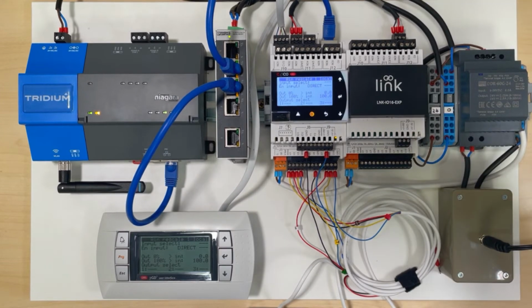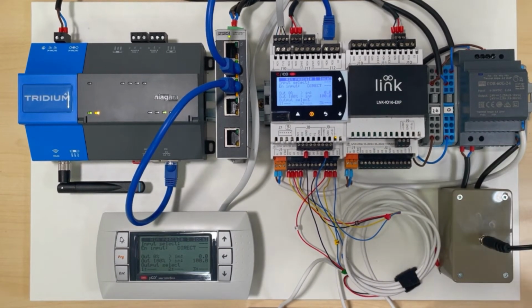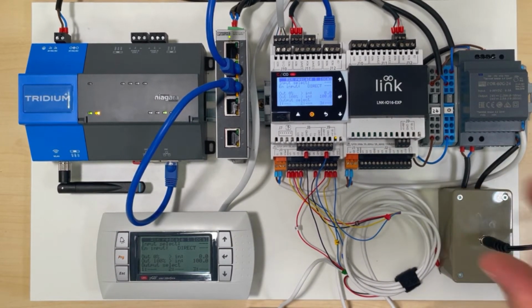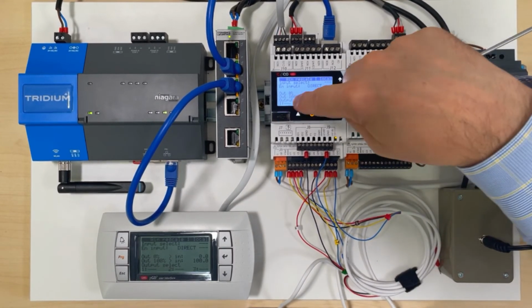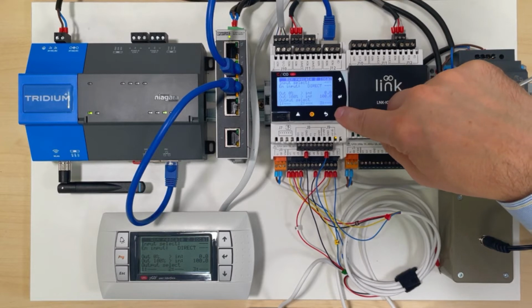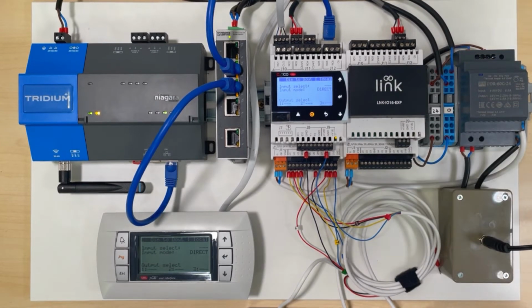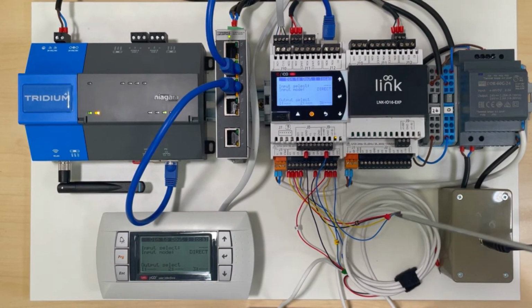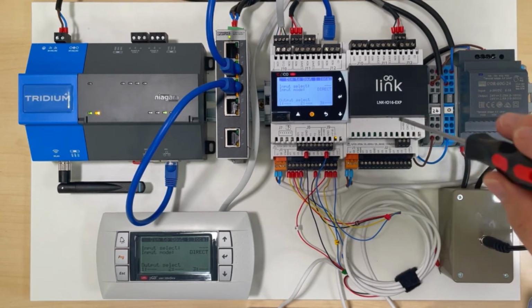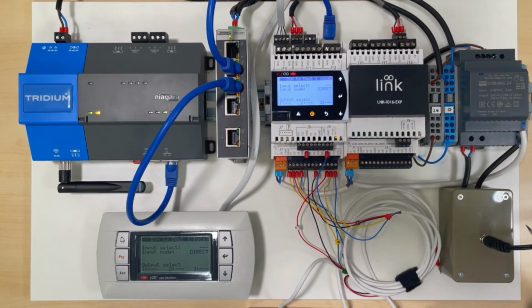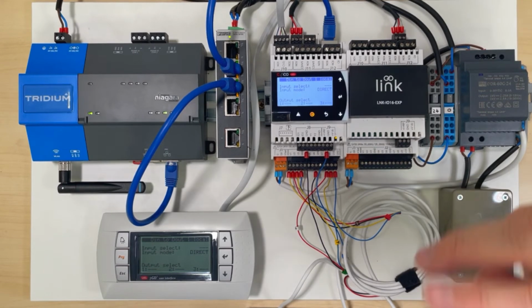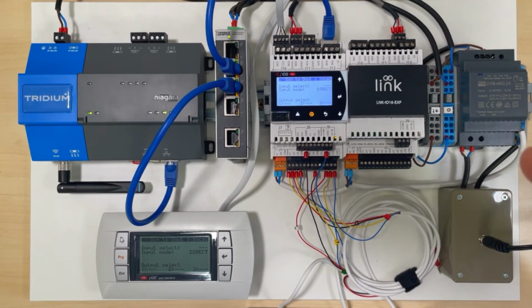You could do an analog input rescale, so what that will do is take a 0 to 10 volt and it will convert it to a 0 to 10 volt on 1 or up to 3 actually of the outputs that you can set down the bottom here. Okay, so there's 2 of those. There's a dig in to dig out, so that's just basically a digital input being mapped through to up to 3 digital outputs, and you can reverse it, so when the digital input is on, it can be direct and the digital outputs will be on, or it could be indirect and the digital outputs will be off, however you want to set that up.